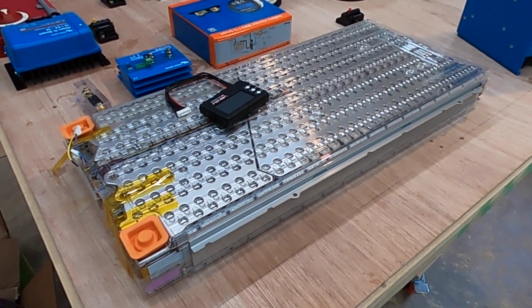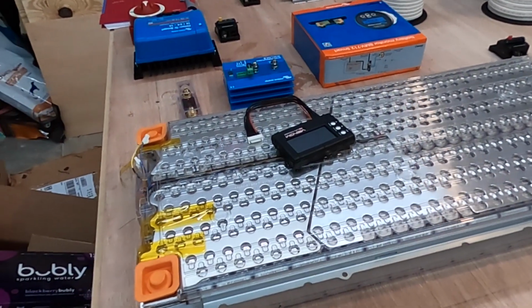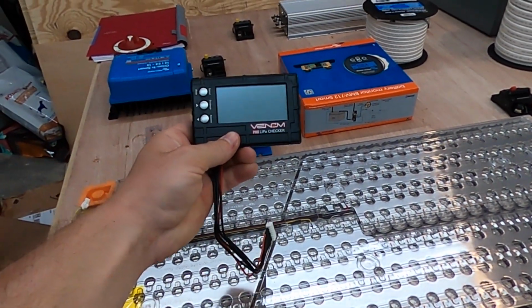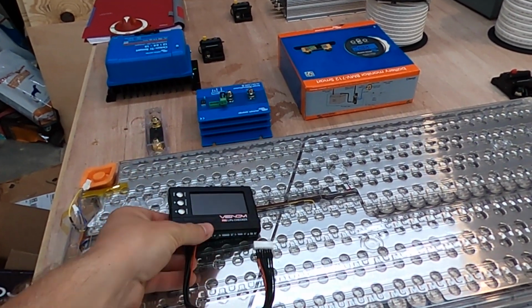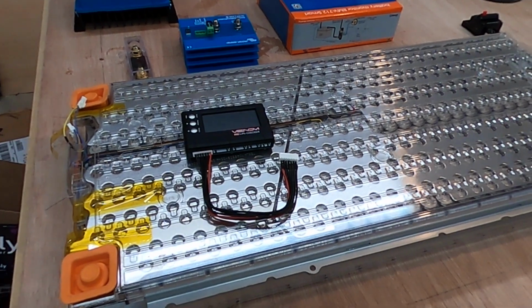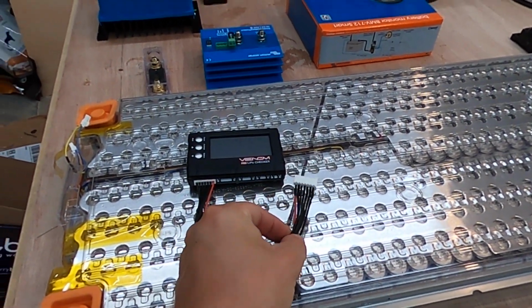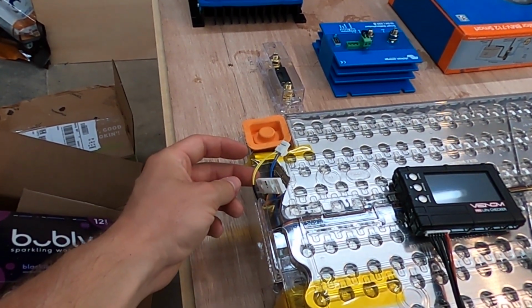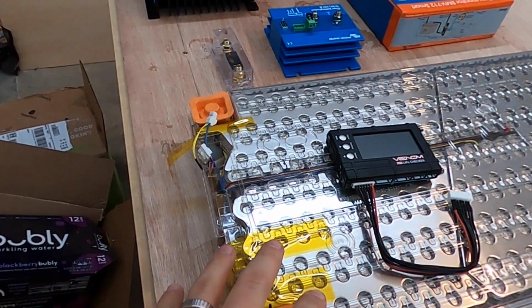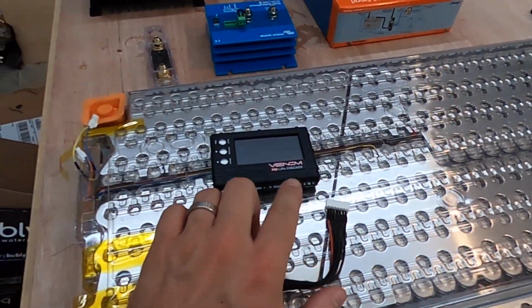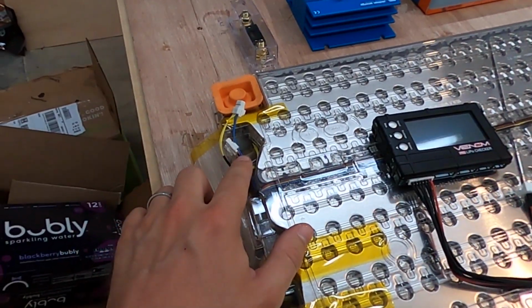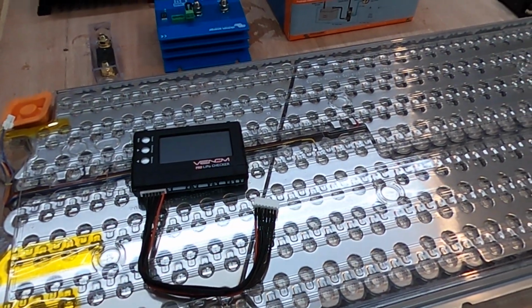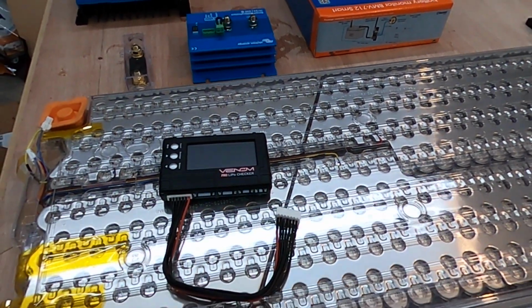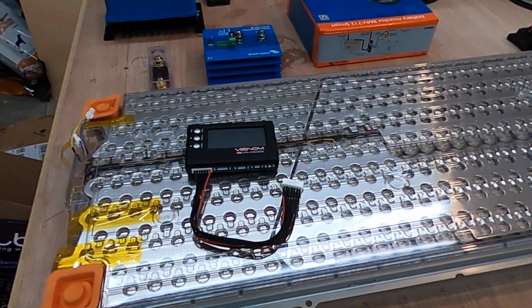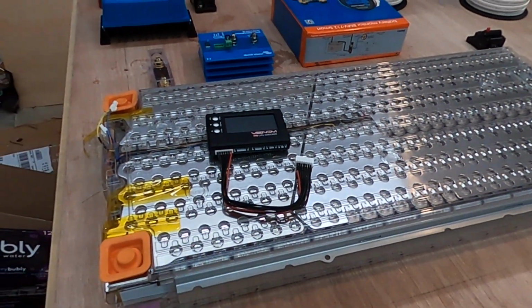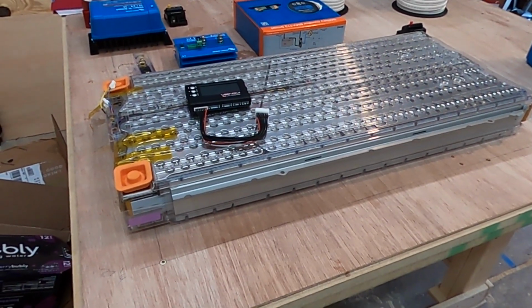Another thing to keep in mind if you're going to run a Tesla battery module is you really need a way to balance the cells. That's where this comes in - a Venom Pro Lipo checker with a 6S connector. I'll have to do some soldering because this connector isn't compatible with the Tesla battery module connector. I've got the wiring schematic for both units, and I'll solder these wires together, giving me the ability to balance the different cells in the pack and make sure none of them go bad. So those are basically the main points on the Tesla battery module.